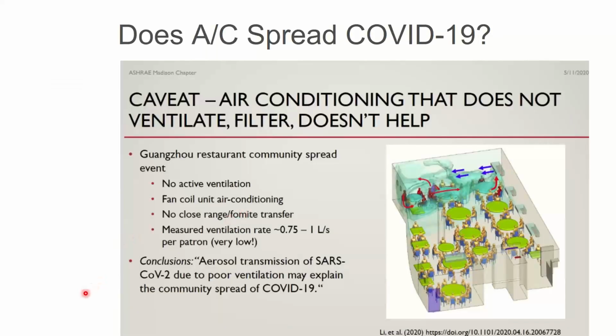So the good folks at ASHRAE have researched this. This one comes from an ASHRAE Madison chapter, but ASHRAE National and other chapters as well have all taken a look at this exact restaurant application, this exact one in China. And this is kind of the information that was found. First off, they had 4 ductless mini splits in there. So as you guys know, ductless mini splits are not known for their fresh air ability. You can combine them with dedicated outside air units, and then you can get some really good fresh air. But just on their own, they don't really have any fresh air coming into them.